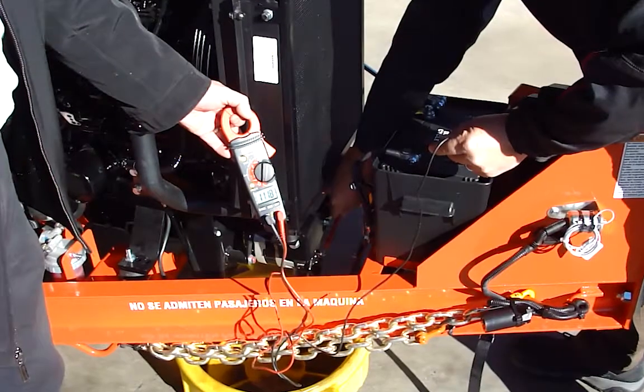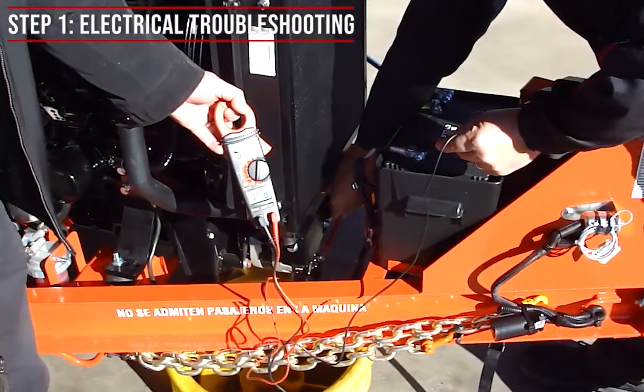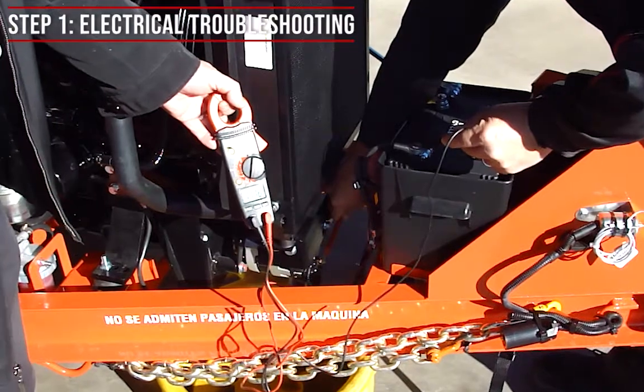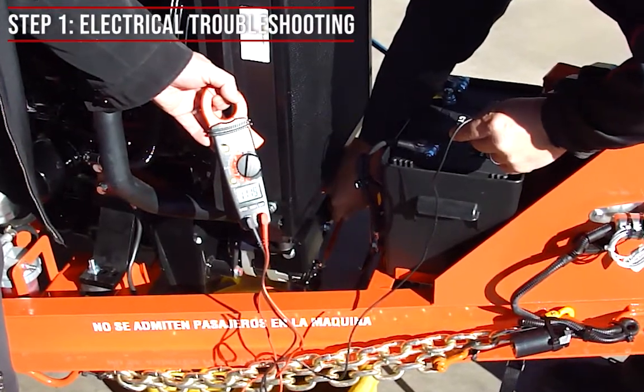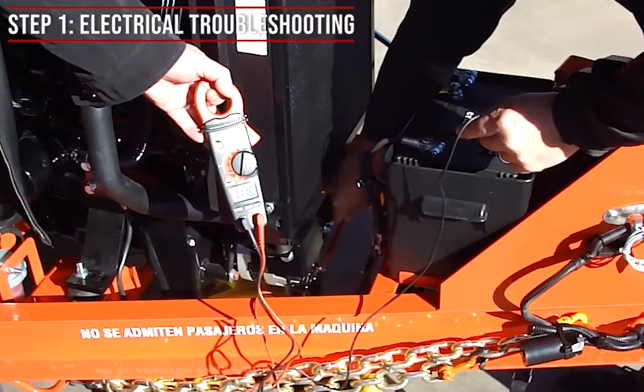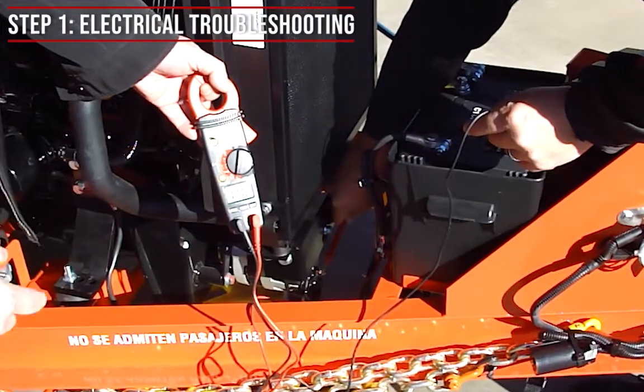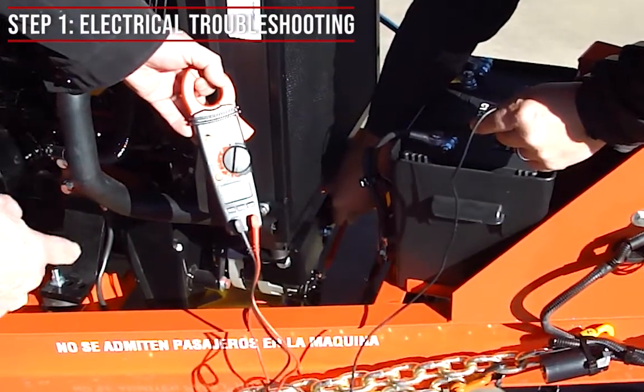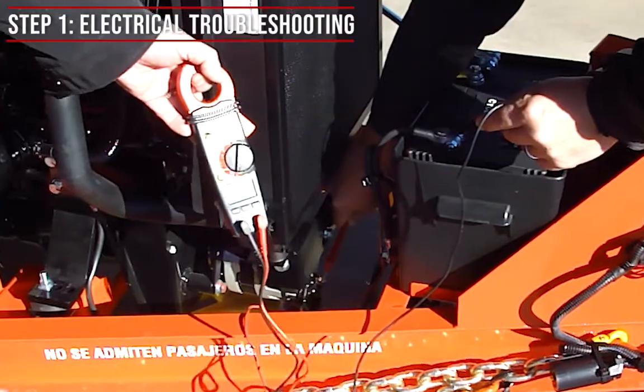Step 1 of electrical troubleshooting. We're going to check and see if there's 12 volts between the bat terminal of the generator and a nearby ground source. We often use the battery for this. If yes, you have 12 volts, you'll continue on to the next step. If no, you're going to go to step 6 of electrical troubleshooting.